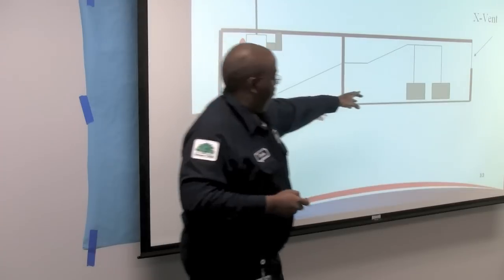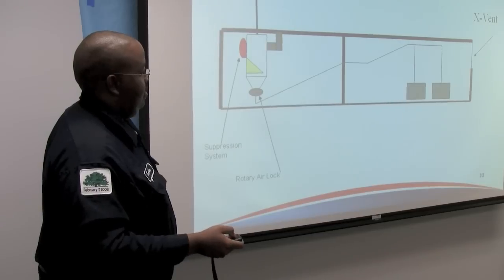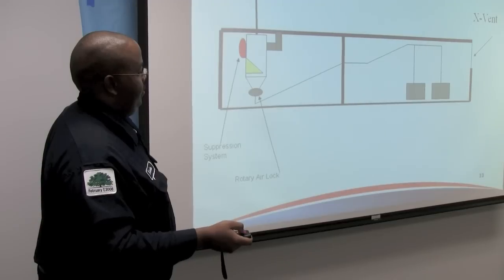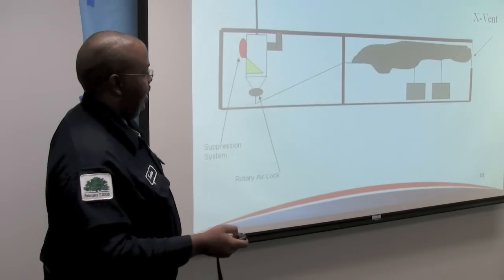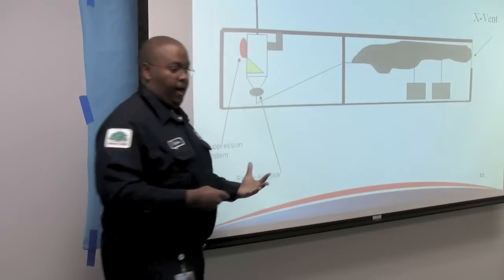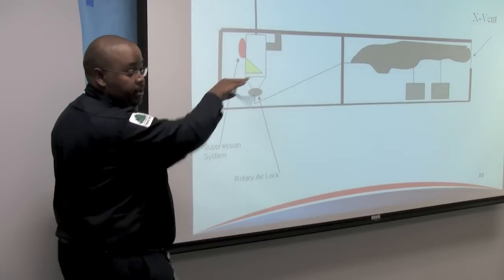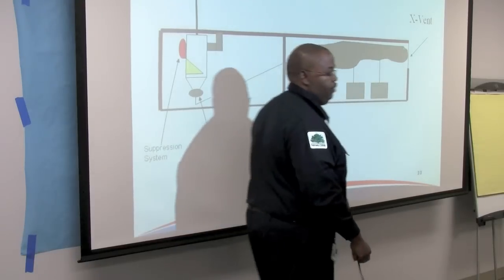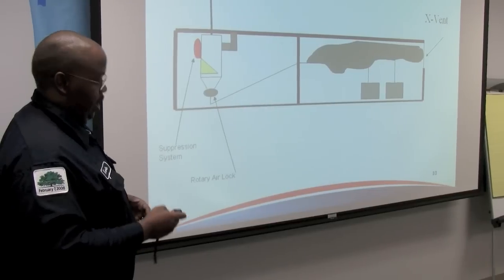In another scenario: primary deflagration, shock wave, residual shock waves flowing through, then a suspended cloud. Here, we've installed segregation and isolation barriers — firewalls or rated walls — and an explosion vent on one side, directing the explosion where we want it. Per NFPA standards, you don't vent to an area where there are things you care about: people, significant property, structures.